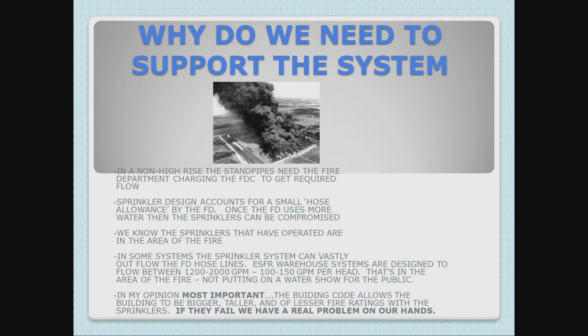All right, so to me, this is really important that we talk about this, and that is, why do we need to support the system? When I worked in Fairfax County in the fire marshal's office, we got a call to come out and look at a system, sprinkler building. It didn't put the fire out. There was more damage than they had expected. And we went out there, and the fire line tape was tied to the FDC, but nobody had ever connected to the FDC. They had never supported the sprinkler system.